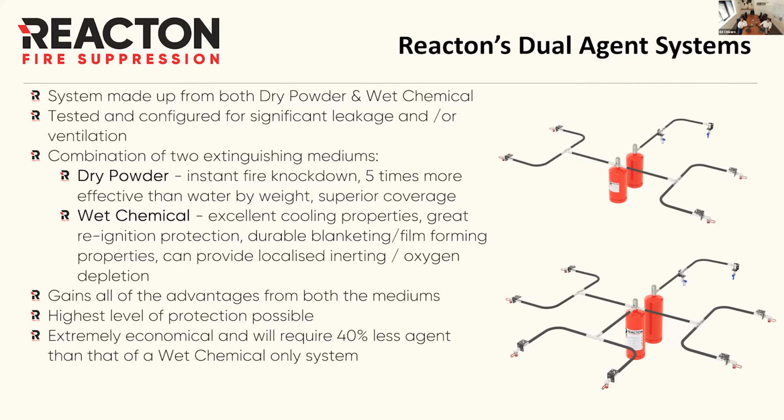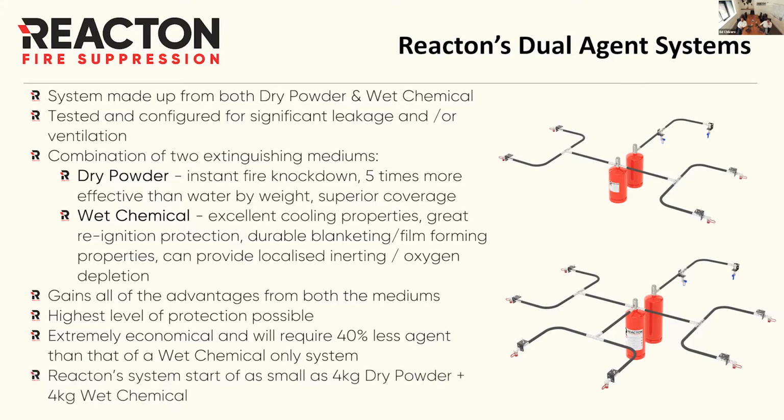And then the fact of having these two agents, you get all the advantages from both mediums in a single solution, highest level of protection, as I mentioned, and then it's very economical compared to just a wet chemical or liquid-based system. And then just to give you a little fact at the end there, Reacton systems start as small as a 4 kilo powder and 4 kilo wet chemical.